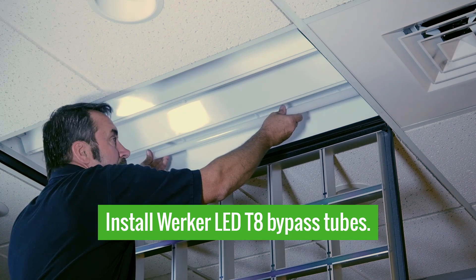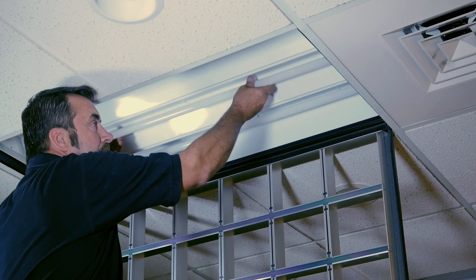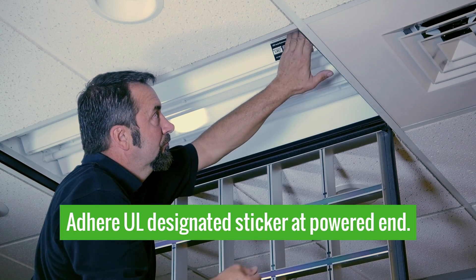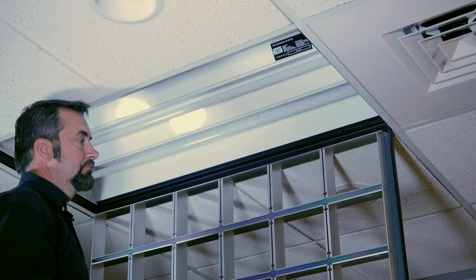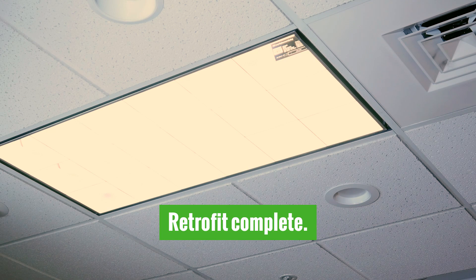One key thing to remember: there is power to only one end. And once the three tubes are installed, one last piece is going to be to adhere on the power end of the fixture the UL designated sticker to indicate this fixture has been retrofitted and no longer complies with standard fluorescent tubes. At this point, we can go ahead and reapply power at the breaker. And we've just retrofitted to Werker LED T8 bypass tubes.